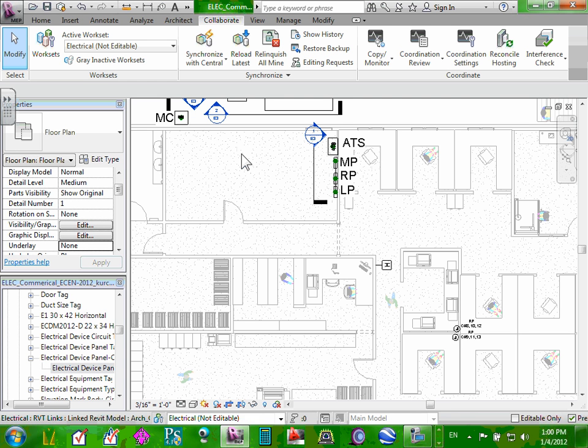It's just a receptacle, no junction box. And open office 126 north and east, one double duplex, a quad on wall per cube for data equivalent. So you really end up with one quad and one duplex for every cube that's on the north and east wall. No power connection.